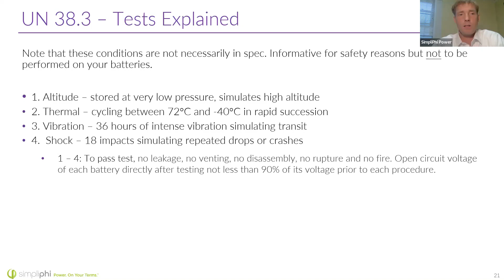Then there's an external short circuit test. In this case, we heat the battery up, it's heated for 6 hours. I don't know a lot about this test, but it's heated up, and then we short circuit the battery and make sure it's not going to go into thermal runaway. This would not work for cobalt-based chemistries — short circuit one of those batteries, and more likely than not they're going to go into thermal runaway and catch fire. So this is done: short circuit the LFP battery, it still stays below 170 degrees Celsius and does not catch fire. Again, SimpliPhi's batteries have passed this 38.3 test.